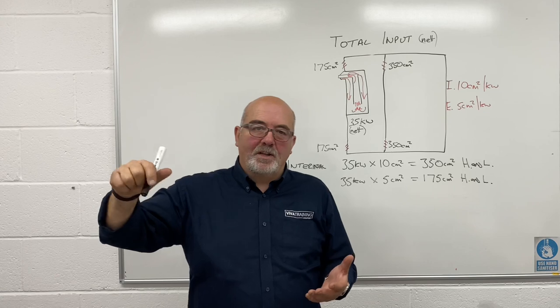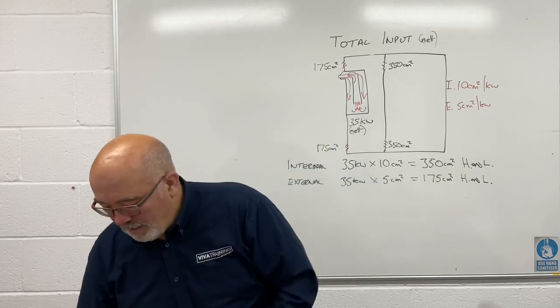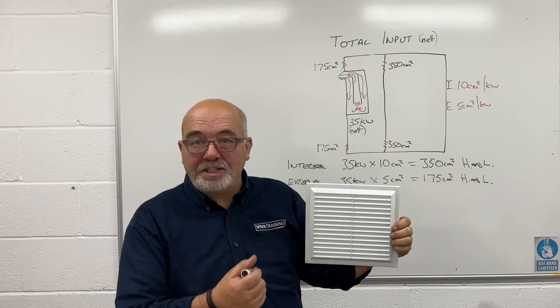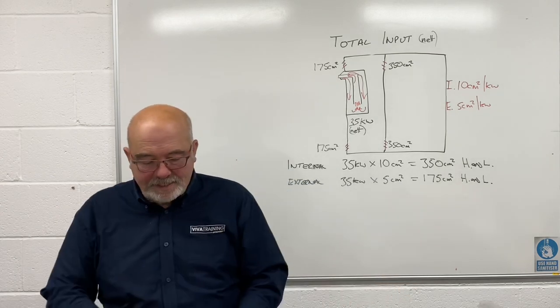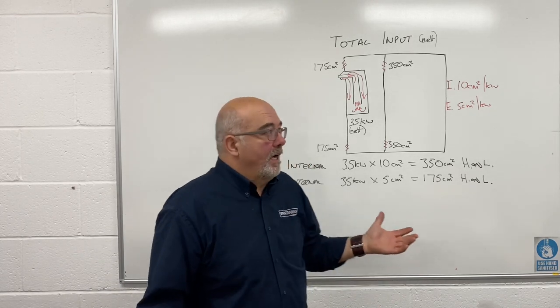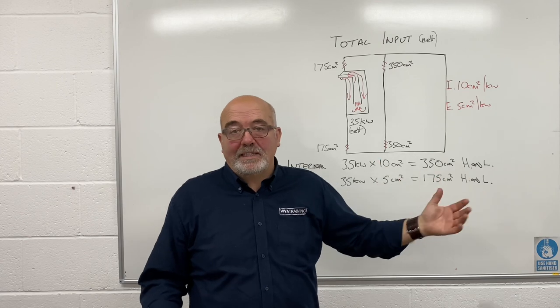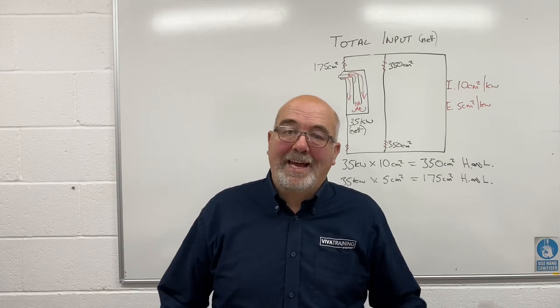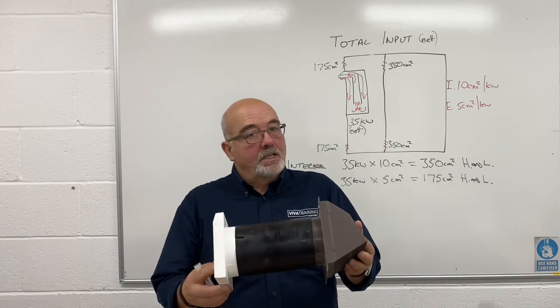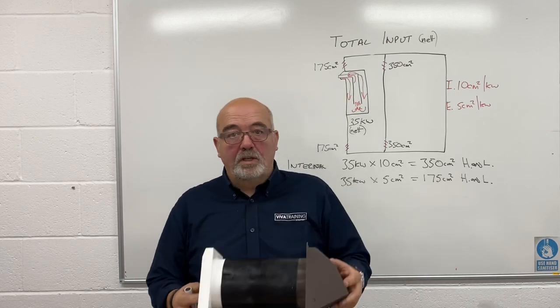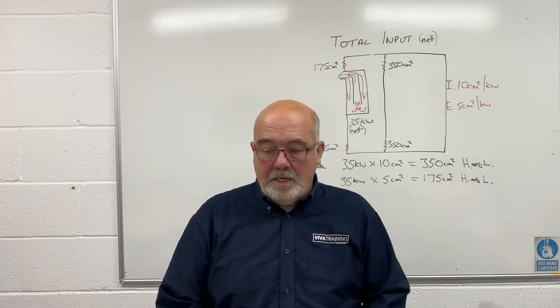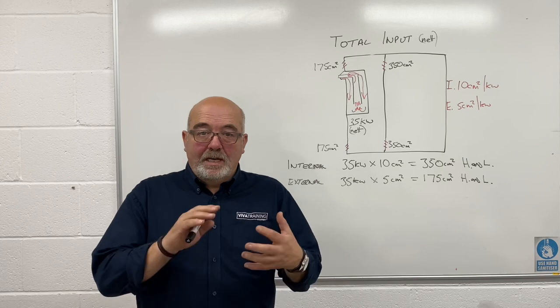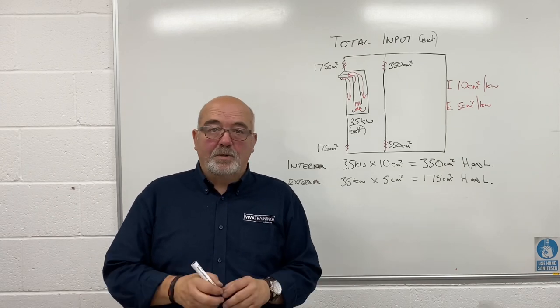Internal vents are no different to external vents really — they must be non-closable, no mesh, all the usual things. For external vents, if it's a single wall such as an outhouse, it's the correct size that matters. But if it is going through an external wall, be aware you still need to consider sleeving that vent through the wall — it still needs to be sleeved. Read your manufacturer's instructions and the publications. Any comments, please come back to Alan and we can sort something out.